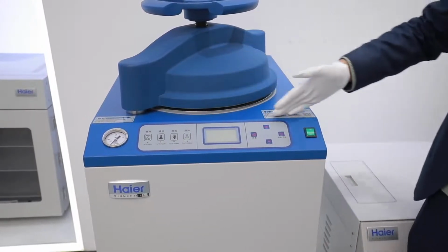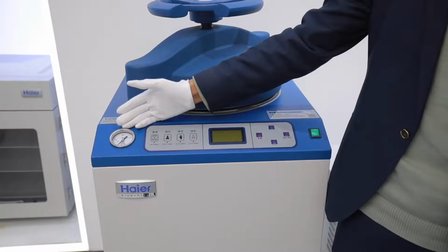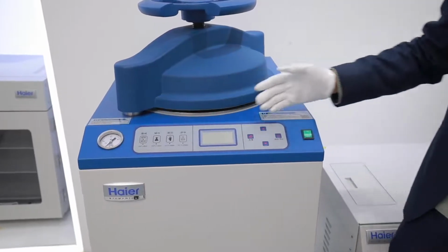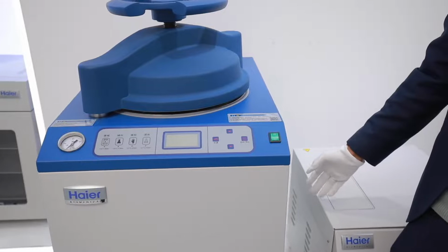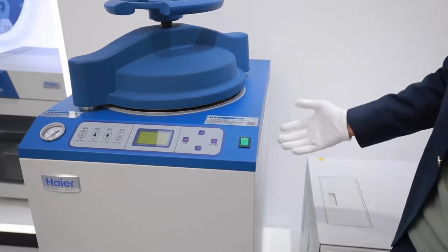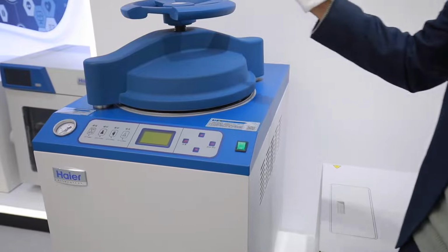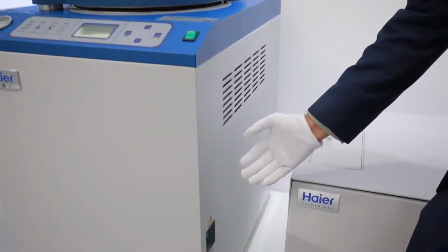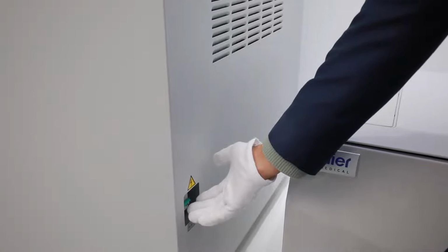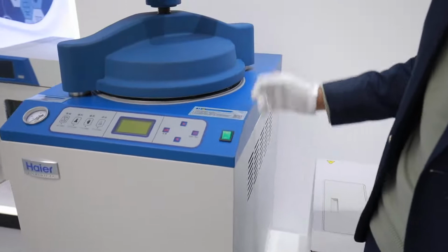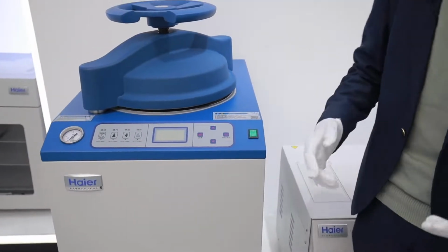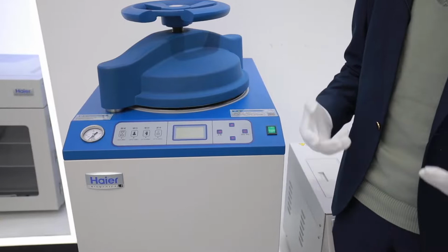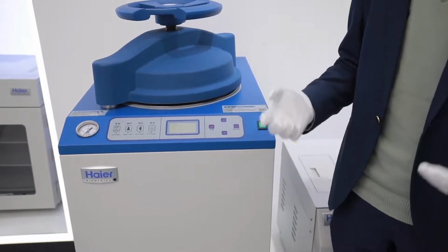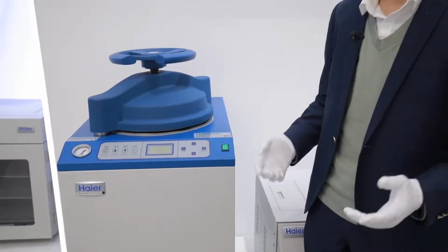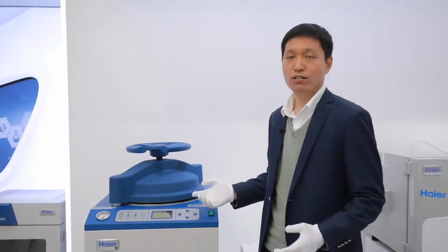Beside the control board, you will see a pressure meter set to monitor pressure inside the chamber during sterilization for safety concerns. The safety features of this sterilizer include overpressure protection, over-temperature protection, and anti-drying protection. The acoustic buzzer alarm will sound in case of any failure during sterilization. The buzzer alarm will also be activated upon the completion of sterilization.